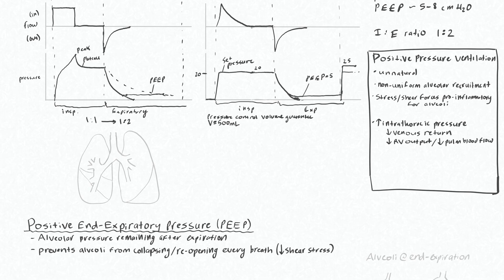What Pressure Control Volume Guarantee does is deliver a couple of breaths and determine the compliance of the patient's lungs — how much volume you can get for any set pressure. After it figures out what pressure will give you a tidal volume of 500 mils, it starts delivering that pressure. This is nice because it allows you to use a pressure control mode while also ensuring you're getting reasonable tidal volumes. But you still have to make sure your pressure doesn't get out of control in a low compliance situation.